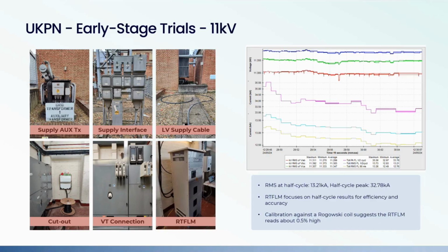Now, at this stage, it was a very early stage result. What I'm depicting here in the graph is less than a minute of recording, and bear in mind that this was the very first recording that we captured, but we were already seeing meaningful results. The data captured on site shows that the RMS fault level current recorded was 13.2 kiloamps, while the peak was just under 33 kiloamps.